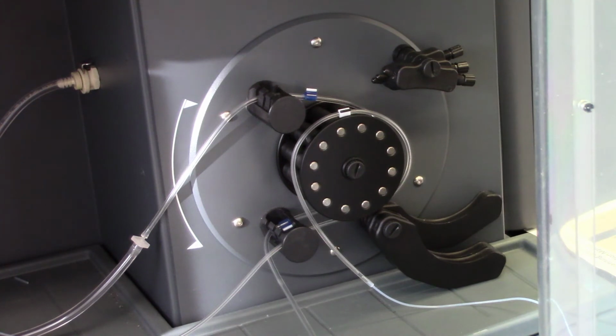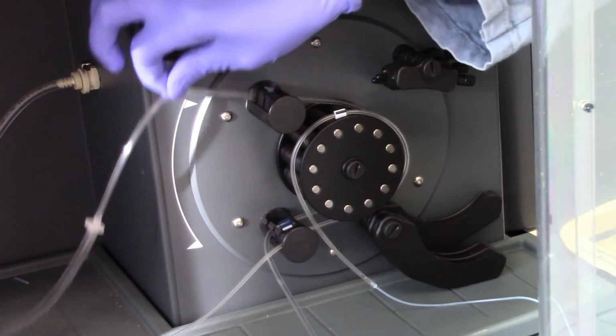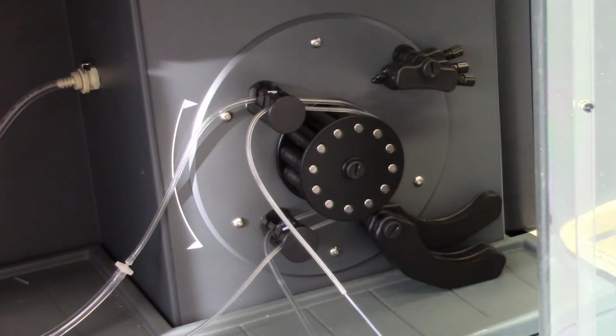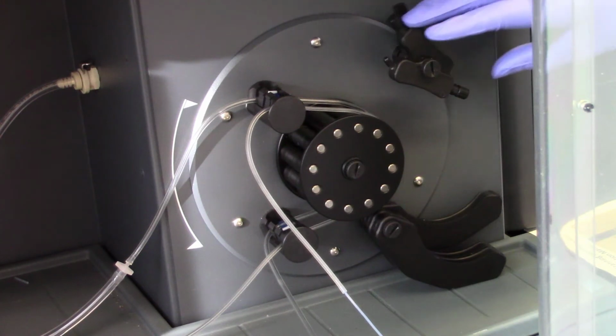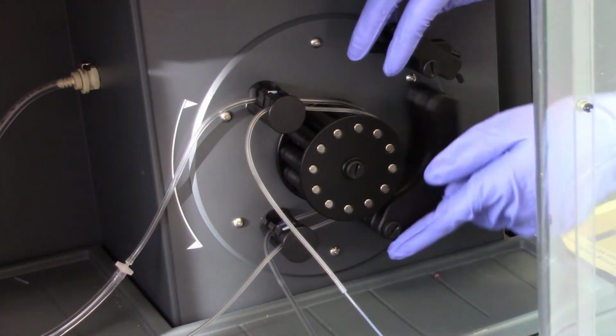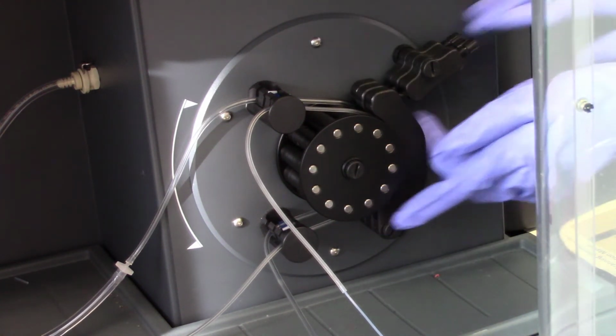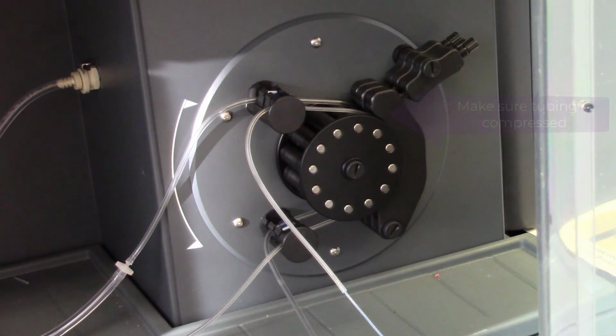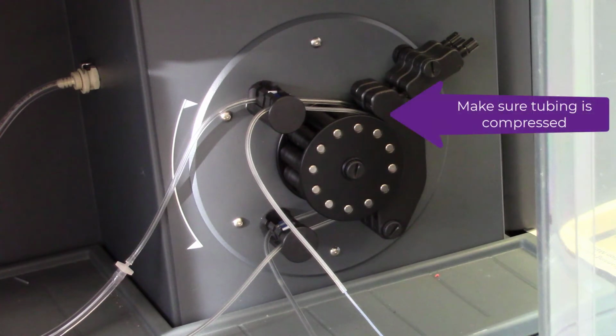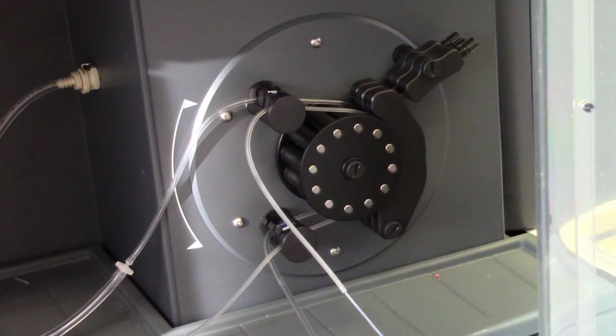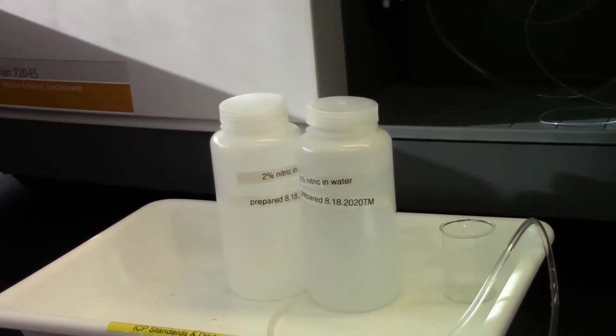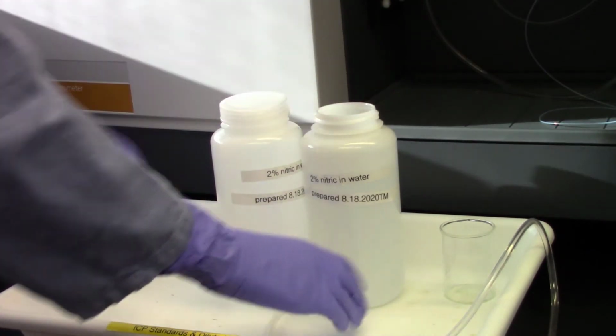After confirming that the tubing on the ICP itself has not gone flat, stretch both tubes and secure the blue and white tabs in the rear and front positions of the holder. Lift the compression pieces and gently snap them into place. Look to be sure that the tubing is in the right position, taking time to readjust if one or both have slipped between the compression pieces. Insert the rinse tube into a solution of 2% nitric acid.